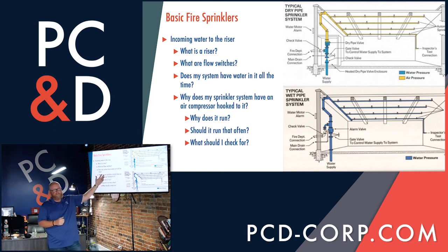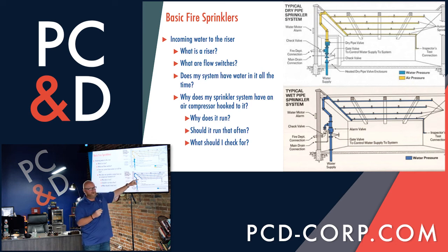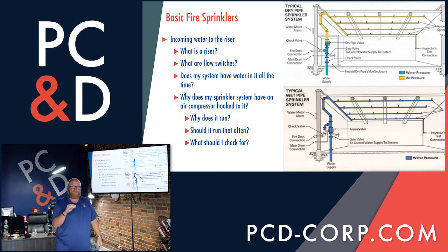The functionality of the heads is the same. So when you have a head on the dry side or the wet side that reaches a temperature, if there's a fire and it reaches 155, 160 degrees, and that head trips, that will enable whatever's behind it, whether it be air or water, to start its travel through the pipe. On a wet system, when that head trips, your water's instantaneous. It's there right now. On a dry system, you have to release the air. So when that head first trips, you will literally hear the system let out a spew of air.